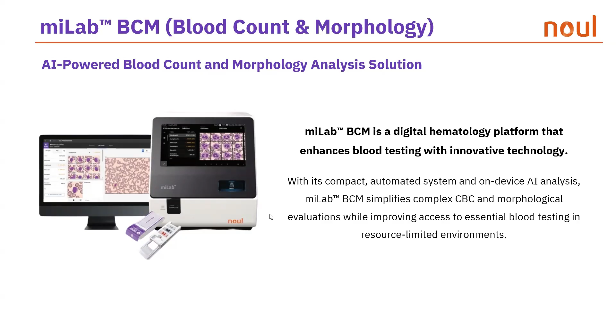Oh, so all the manual smearing, so from the sample loading, that is completely simple. With 5 microliters of blood, you will place the sample in our cartridge. The cartridge will be introduced in the device. The device will perform the smear, the fixation, and the staining, a full automatic process. Then optical imaging starts to collect all the images, and afterwards on-device AI analysis will deliver the results on screen. So this is the intelligent automated workflow without any manual work, guaranteeing standardization and traceability for the whole process. Next slide, please.